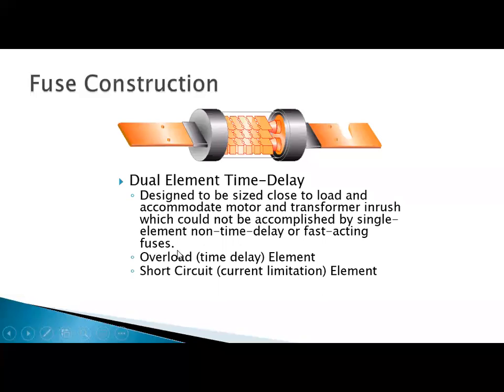And so we're going to allow maybe 10 times the amount of current to go through this on startup of a motor. And then when it comes back, this will definitely help protect against short circuits on a motor, no doubt about it. Of course, on a motor circuit, we have overloads that help us with the overload protection. But dual element time delay is used a lot where we have a high amount of inrush current.